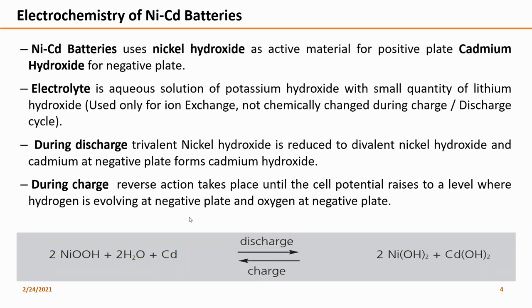In lead acid batteries, ion exchange takes place in the electrolyte, but here the electrolyte doesn't undergo any chemical process during charging and discharge cycles. During discharge, trivalent nickel hydroxide is reduced in the positive plate, and the negative plate forms cadmium hydroxide. The charge and discharge cycle is balanced, so only this reaction occurs between positive and negative plates.